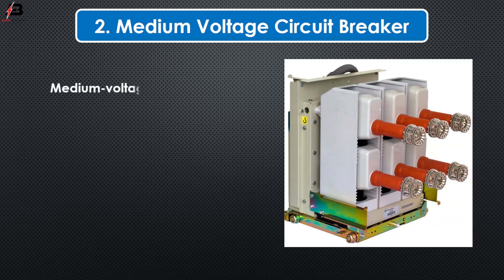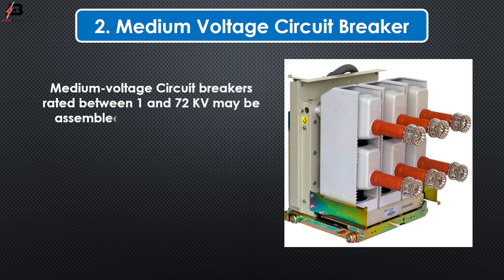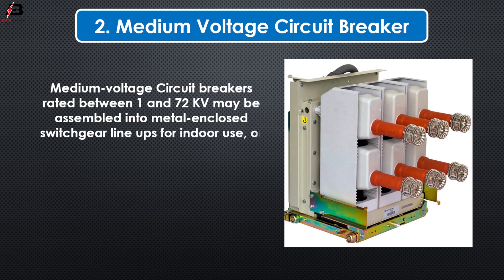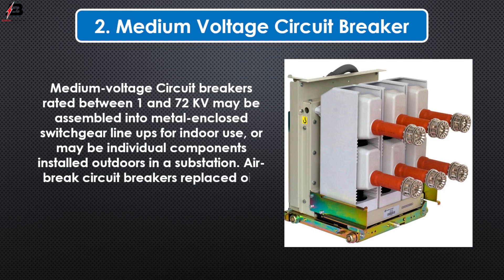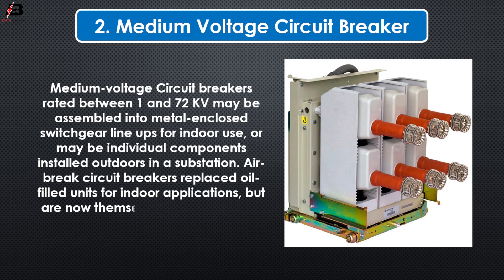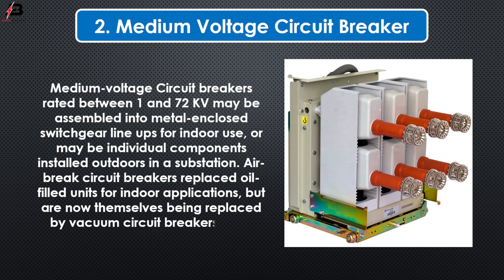Medium voltage circuit breakers, rated between 1 and 72 kilovolts, may be assembled into metal-enclosed switchgear lineups for indoor use, or may be individual components installed outdoors in a substation. Air circuit breakers replaced oil-filled units for indoor applications but are now themselves being replaced by vacuum circuit breakers up to about 40.5 kilovolts.